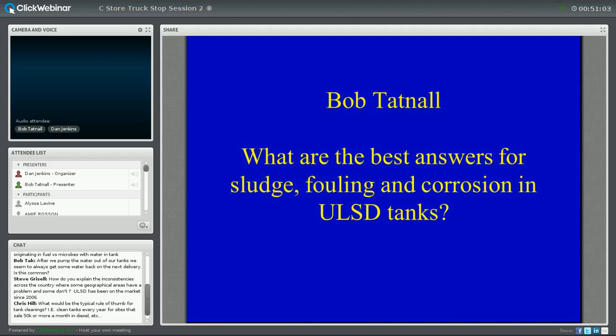It's unfortunate. Years ago, I was consulting for a big gas station chain in the southern states. They were getting a lot of water in their tanks, and they were pumping a lot of water into automobiles and buying a lot of replacement engines as a result. And they asked me to come see what the problem was all about. Well, I found all kinds of reasons for water in their tanks. Some of the older stations had the fill point where they filled the underground tanks at the lowest spot on the apron. So every time it rained, the fill spot was in the middle of a small lake.